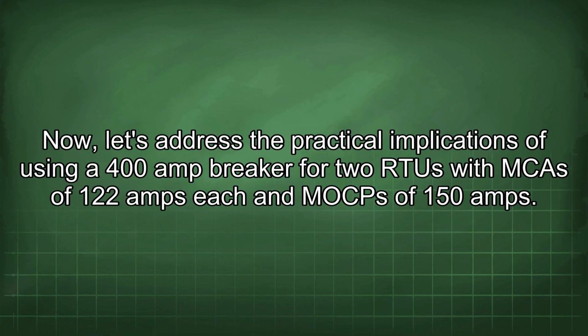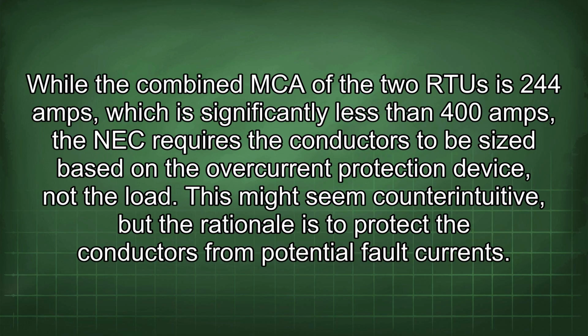Now, let's address the practical implications of using a 400 amp breaker for 2 RTU with MCA of 122 amps each and MOPs of 150 amps. While the combined MCA of the 2 RTU is 244 amps, which is significantly less than 400 amps, the NEC requires the conductors to be sized based on the overcurrent protection device, not the load. This might seem counterintuitive, but the rationale is to protect the conductors from potential fault currents.